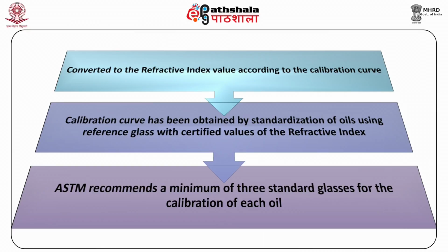The calibration curve has been obtained by standardization of oils using reference glass with certified values of the refractive index. ASTM recommends a minimum of 3 standard glasses for the calibration of each oil.